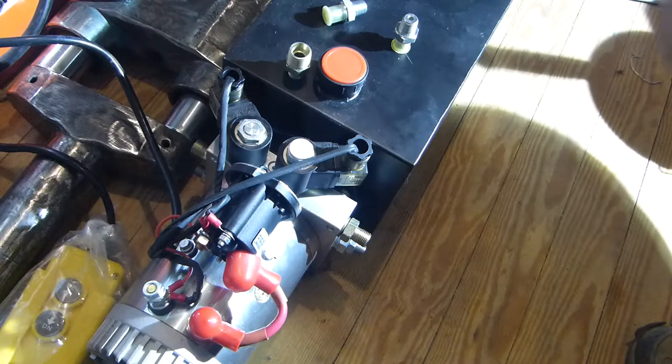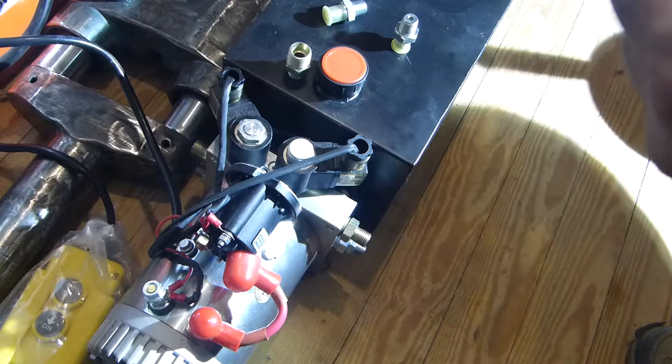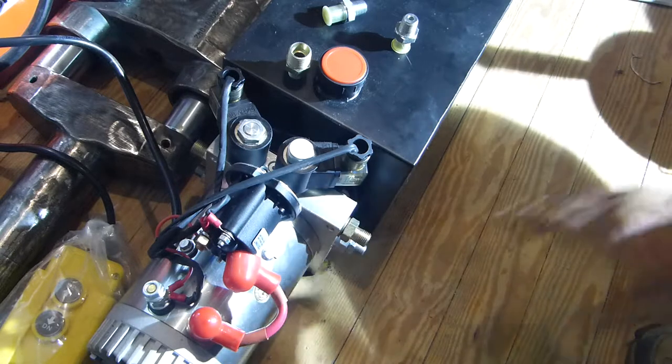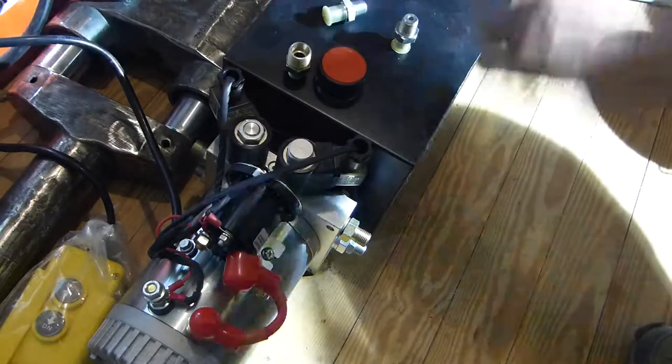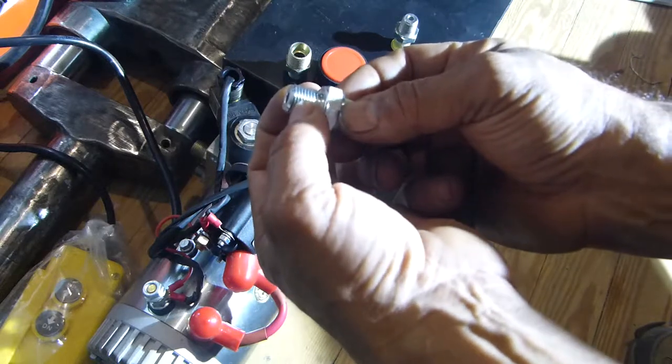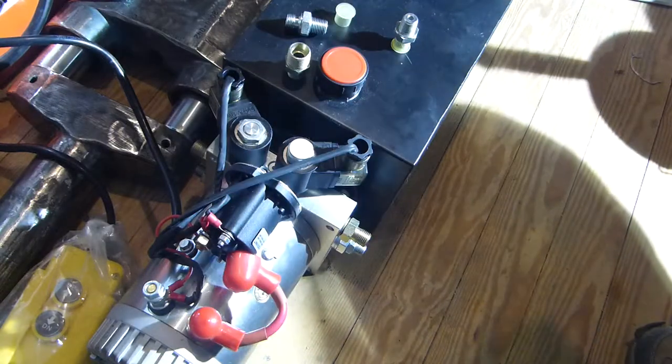So your tapered threads will still work. BSP - British Standard Pipe Thread parallel threads, right, these are parallel. So if you're not sure, you'd measure. Parallel means you measure here and you measure there, not the very tip but maybe two threads back, and they're all parallel. The measurements is parallel.